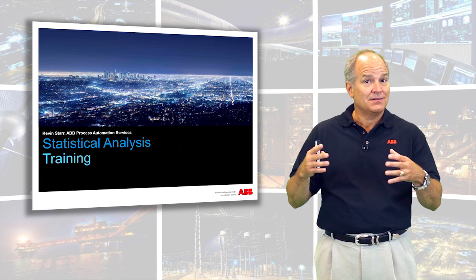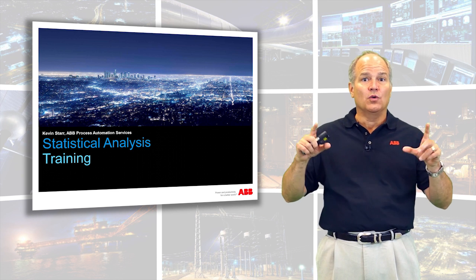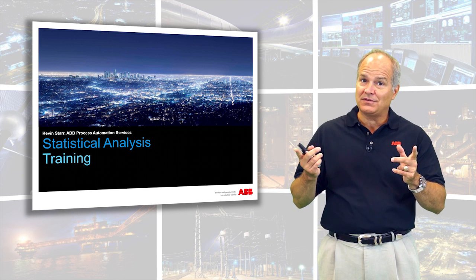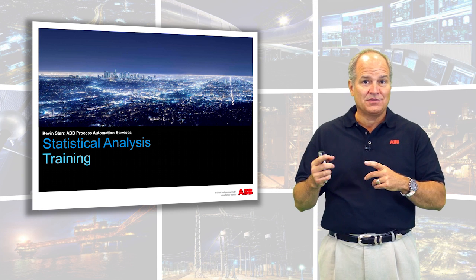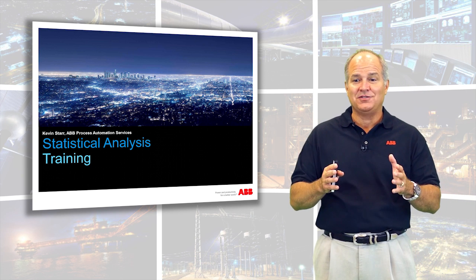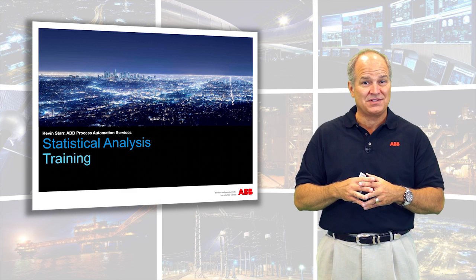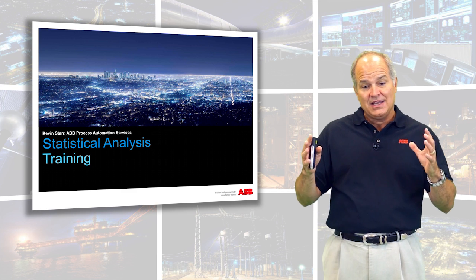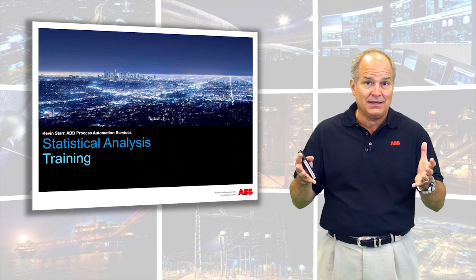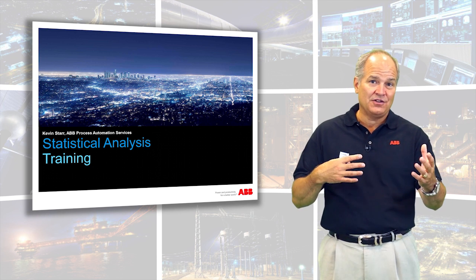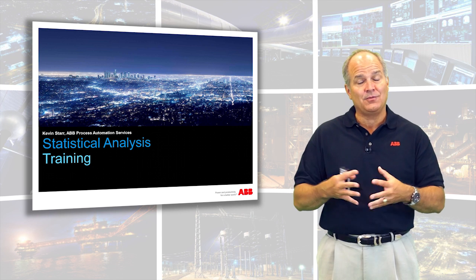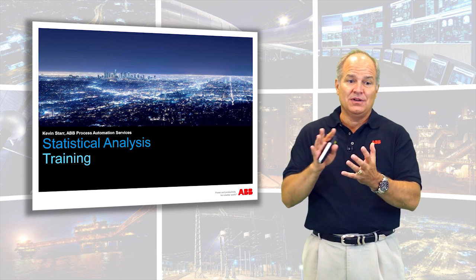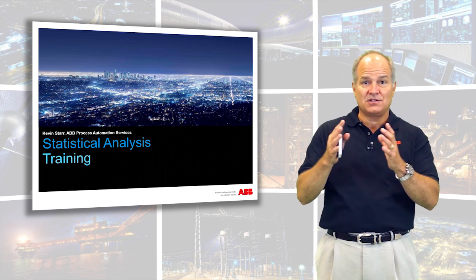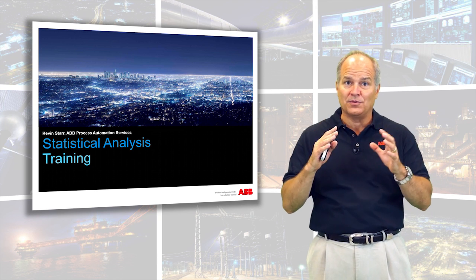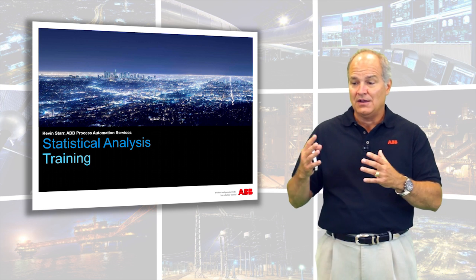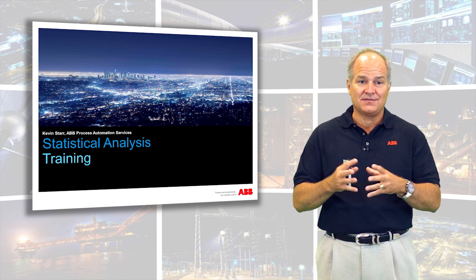We talked about sigma, or standard deviation, which is a measure of how normal a data set is. Remember the 1, 2, and 3 sigma and what those values are. 1 sigma is 68%, 2 sigma is 95%, and 3 sigma is 99.7%. Those are just telling you statistically where your data will be. We talked about control charts and how you can use those to better define what an alarm is. Then we went into kurtosis and skewness. It's a way to measure how normal your data set is, and we talked about how you could relate those to physical problems in your process if it's not normal.